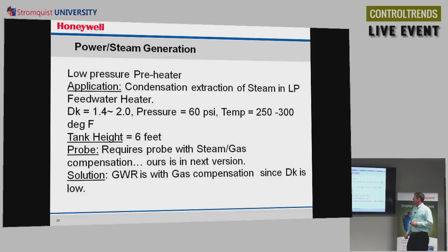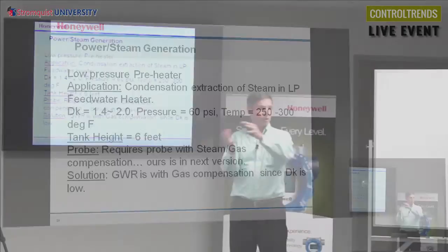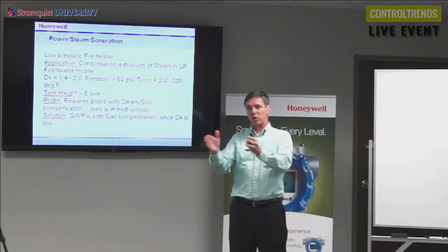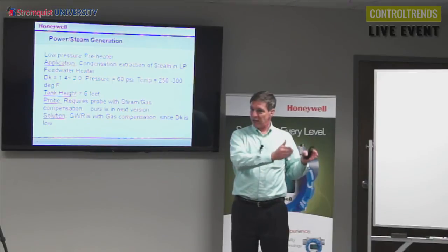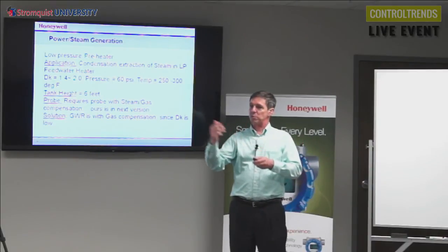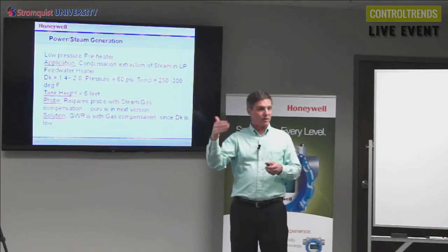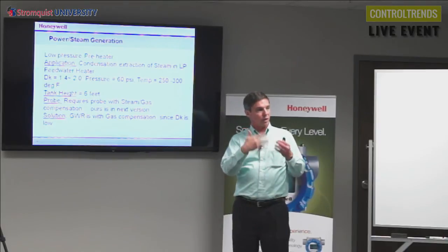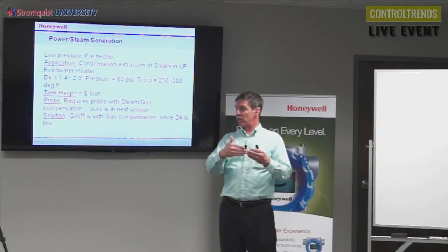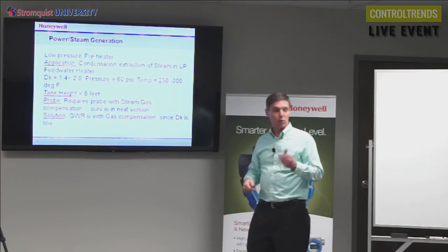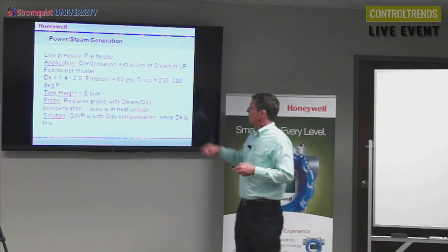And here's a particular application we're looking at. This is the low pressure preheater. Some people call this a feed water heater. So in a power plant, what they're doing is heating up the water before it goes into the main boiler. And it's going through different stages called feed water heaters. And in each stage, the water is getting hotter and hotter, and it's being heated up by steam. Now that steam that's being used to heat it up will condense, and we're trying to measure the level of that condensed water in one of those stages.